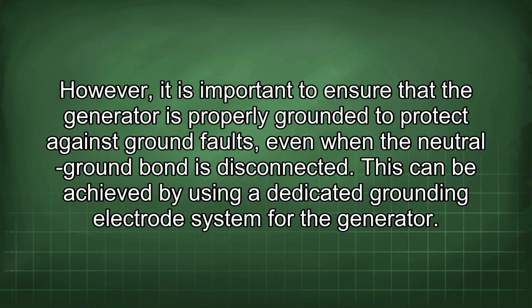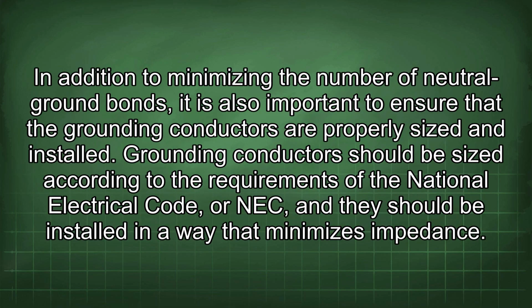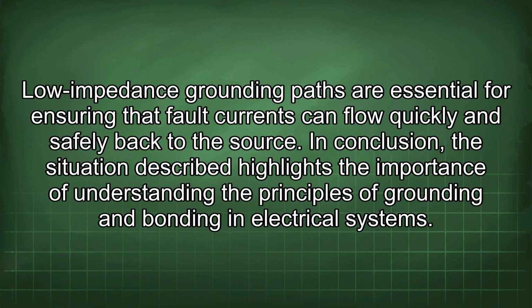However, it is important to ensure that the generator is properly grounded to protect against ground faults, even when the neutral ground bond is disconnected. This can be achieved by using a dedicated grounding electrode system for the generator. In addition to minimizing the number of neutral ground bonds, it is also important to ensure that the grounding conductors are properly sized and installed. Grounding conductors should be sized according to the requirements of the National Electrical Code, or NEC, and they should be installed in a way that minimizes impedance. Low impedance grounding paths are essential for ensuring that fault currents can flow quickly and safely back to the source.